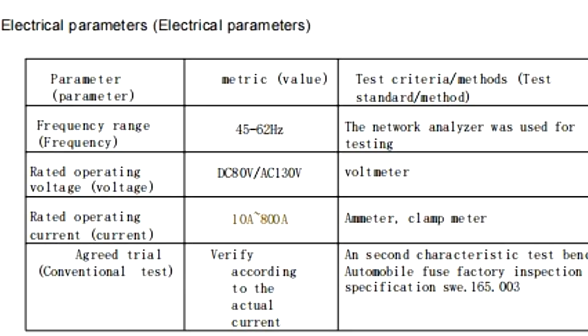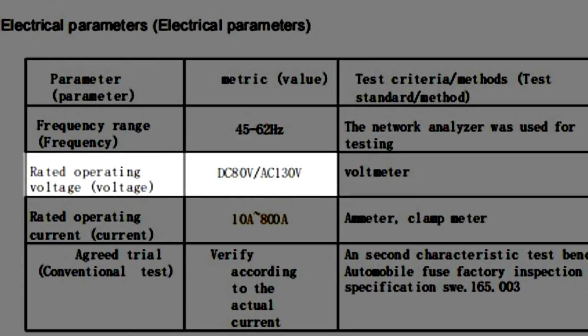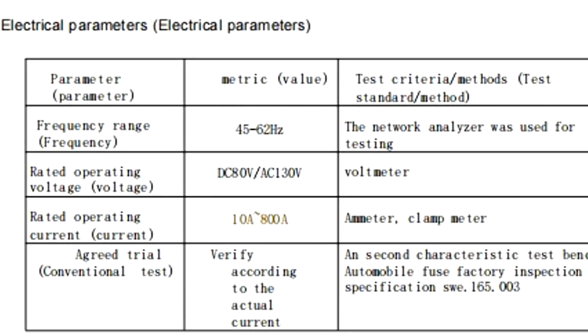Alright, and the second document they provided is the electrical parameters - frequency range, rated operation voltage. Here it says 130 volt AC, so this contradicts the first document a bit. And rated operation current is 10 amps to 800 amps, depending on the model you select apparently. And that's pretty much it. So we still don't have a rated breaking capacity for this fuse.